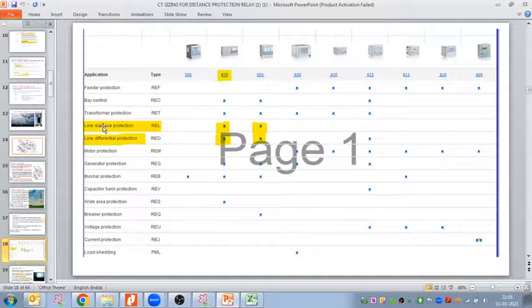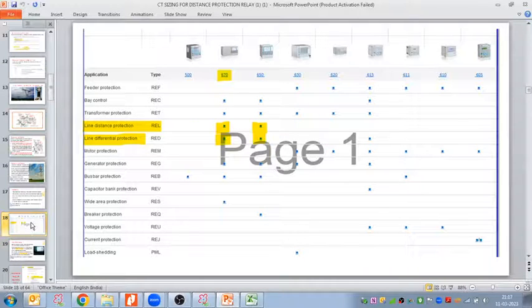Right. So for the line protections, if we have differential protection, we can use RED 670 or RED 650. If we have a long transmission line, we need to select the distance relay. For that, the relay model would be REL 670 or REL 650. All this we discussed yesterday.